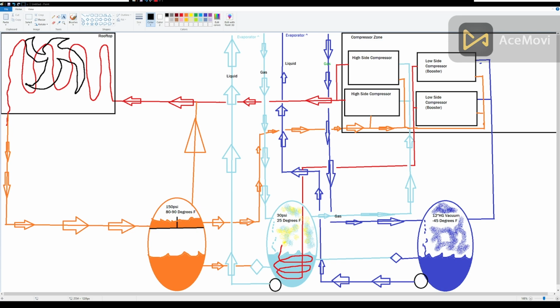So when we go into talking about a vacuum, there's not negative pressure in here. There's like 6 PSI absolute. There's not negative pressure or 0 pressure. It's a vacuum in the sense that it is lower pressure than what you are experiencing right now. If you poked a hole in that pipe, it would suck in because the pressure out here is higher than the pressure inside, but there is still pressure inside. It's just below what every gauge has probably ever told you is 0. But every gauge was lying.